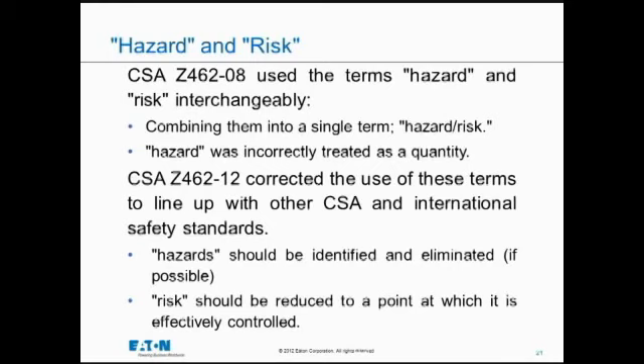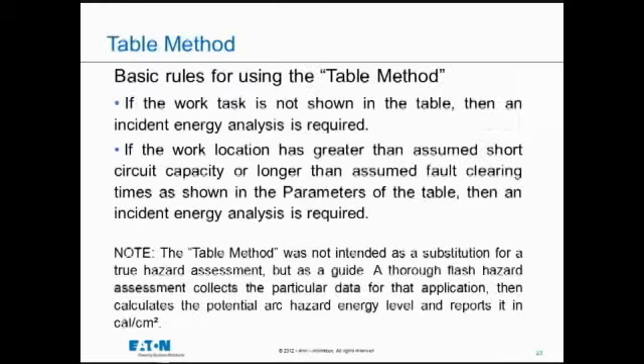There are a lot of rules to using the table method. It is the easy button. You could look up a value in the table method and you've got your arc flash analysis done, but there are a lot of, not a lot, but about 3 or 4 restrictions that you can't use the table method if, and the main ones are they put parameters around short circuit level, they put parameters around fault clearing time from fuses and circuit breakers, and if you fall outside of those parameters, you can't use the table. And that's described in this slide.